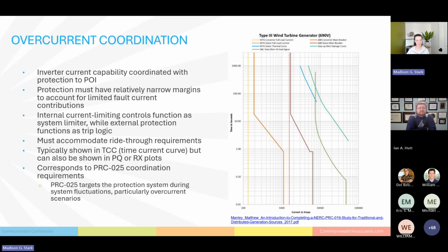This first curve over here, again, we have time in seconds on the left-hand side and current in amps on the horizontal axis. As we read from left to right, current increases, and from bottom to top, time increases. As current increases, the first thing we hit is our converter full load current, the maximum full load current that the converter can output. The next thing we hit is this converter main breaker, the main protection for the converter. That means this main breaker is not impeding the converter's function or internal ability to output current. That's the coordination we're looking to see for a converter.